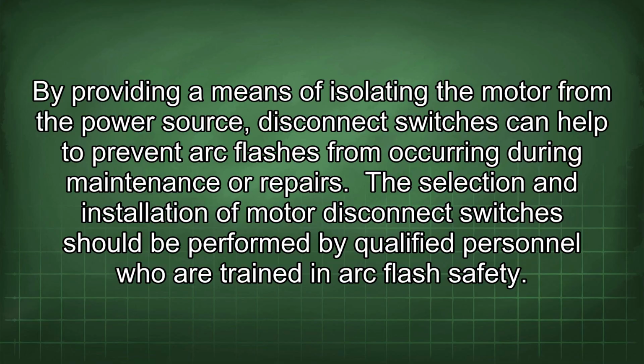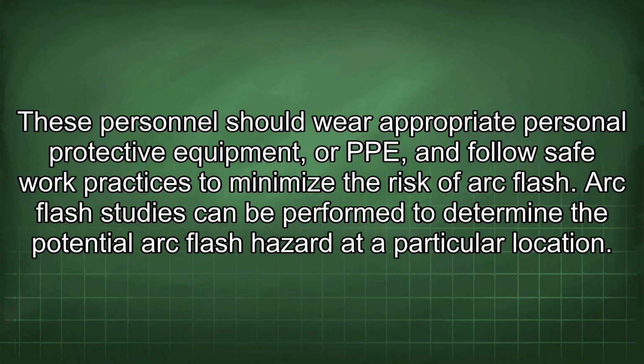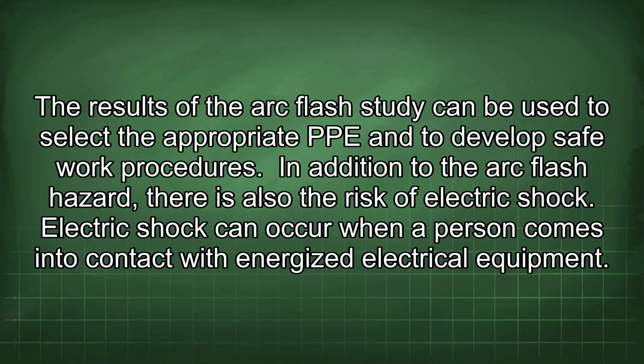The selection and installation of motor disconnect switches should be performed by qualified personnel who are trained in arc flash safety. These personnel should wear appropriate personal protective equipment, or PPE, and follow safe work practices to minimize the risk of arc flash. Arc flash studies can be performed to determine the potential arc flash hazard at a particular location. The results of the arc flash study can be used to select the appropriate PPE and to develop safe work procedures.